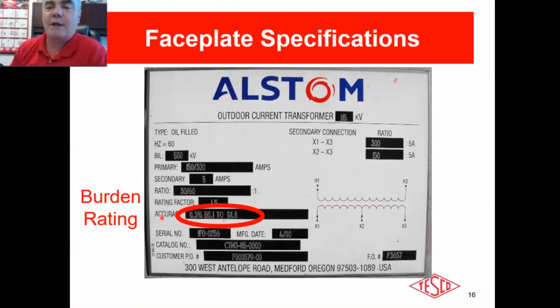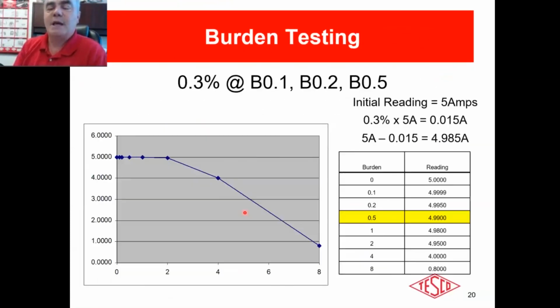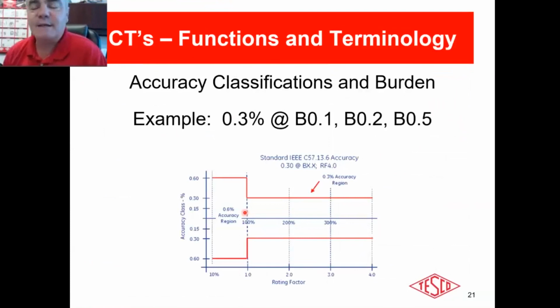That's how you learn that, oh yeah, the faceplate says 0.3. But once you drop below the 400 amps on a 400 to 5 or the 300 amps on a 300 to 5, the accuracy goes in half. It goes to 0.6. That is a mistake that was made for many years by people when they sized CTs for a service. They'd say, oh, well, the customer is generally going to be using 100 to 200, and he could use as much as 800 amps. So they would throw an 800 to 5 CT. Bad idea. You really wanted to throw a 200 to 5 with a thermal rating factor of 4. That was the correct meter. All right. Now, so 0.6, just something that you have to know. You'll never see it on the faceplate.